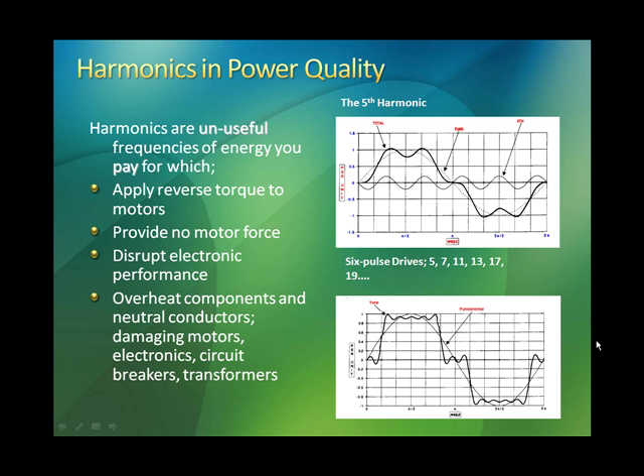It does damage motors. It damages electronics. It damages circuit breakers and transformers. A lot of the same things that surges and spikes do, harmonics do as well. Now in the diagram in the upper right hand corner, you see in the dotted line the typical AC waveform, a nice smooth sine wave is what it's called. And then you see this small ripple right through the middle line. And that is a fifth harmonic that is being put back on the line thanks to something called 6-pulse drives. We'll talk about that in a moment.